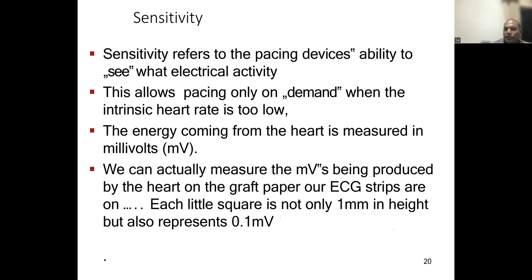So it's like a window. If we program the generator in a way that it can see any electrical activity above a certain level, then it can see everything above that. But then it might also see unnecessary electrical activation. Remember, apart from the myocardium, there are other electrically active structures in the body as well, in the thorax as well. And there can be electrical noise coming from the outside environment. So you have to decide the appropriate range to decide on the exact or ideal sensing level for a particular patient.